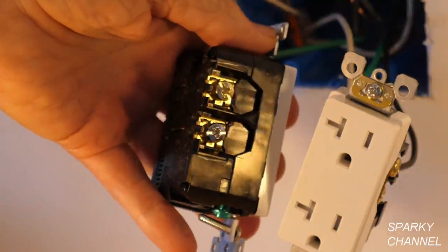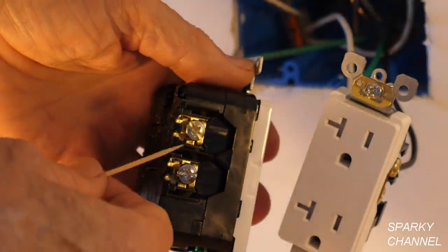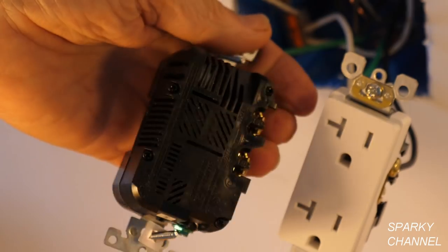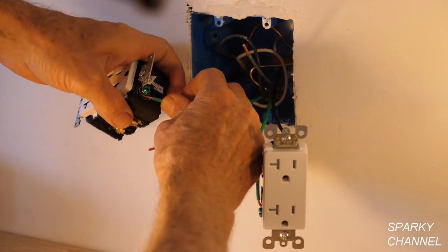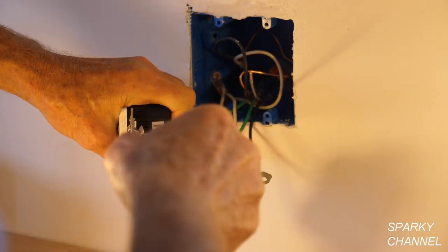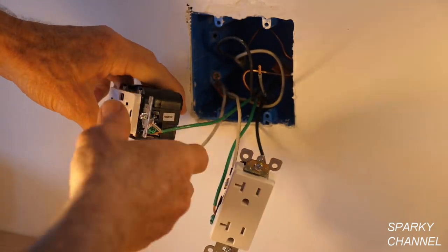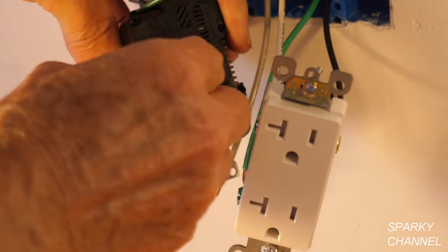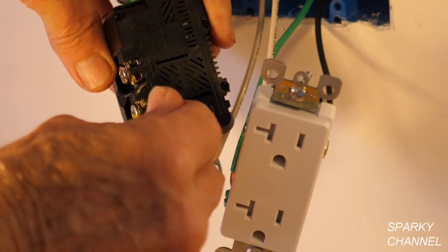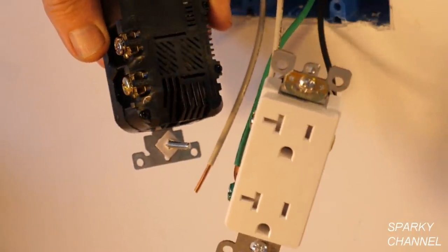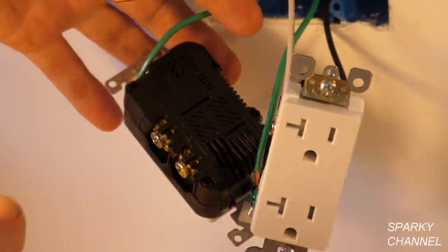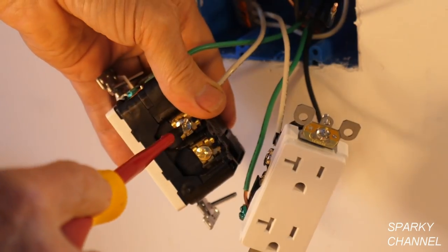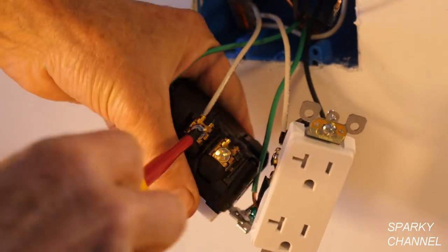This USB device is a little different. It has the silver and the bronze colored terminal on the same side, and this is a vent on the other side. Attach the second green ground wire to the green grounding terminal of the USB receptacle. So this has a different kind of fastening system. You see, it's called a back wire system. The wires just go into here and you tighten it down. It's a very good, very reliable system. It's not a back stab system. Okay, so you put this neutral right in the silver terminal side there. You tighten the clamp down securely.